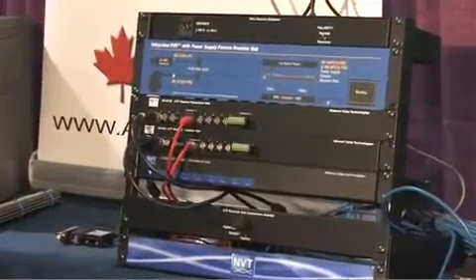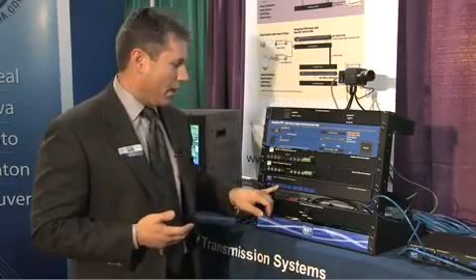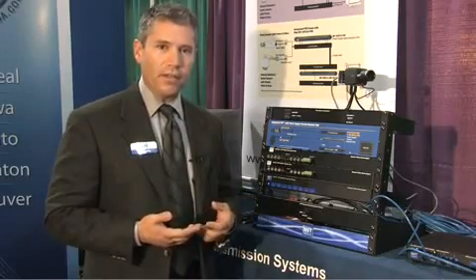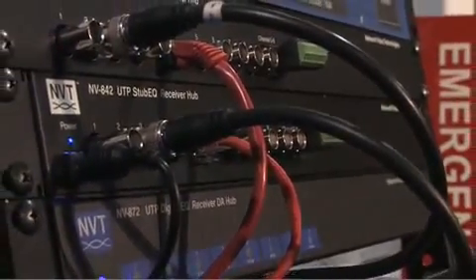One of the products you may not be familiar with at all is our digital equalization product. The practical upshot of this is that it's the only system on the market that has zero gain adjustments from zero feet to one kilometer, and it's going to deliver a perfect one-volt peak-to-peak picture for the most demanding DVR. These also have safeguards built in that'll tell you if there's a problem with your video signal. We have a green light that means it's good, an amber light that means we see a video problem, or a red light that says we have a very severe video problem. Really what it's all about is delivering a quality video signal to a DVR that's expecting a perfect one-volt peak-to-peak signal, while lowering your labor cost because you don't have to adjust anything on the box.